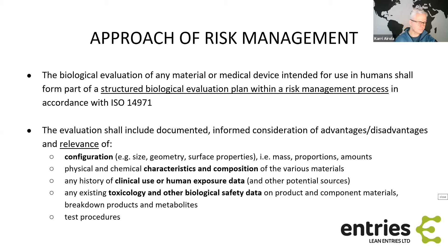So here again, it mentions leachable substances, which refers to parts 17 and 18, and degradation products you should be testing, and you should take into account the packaging materials you're using. Are they in direct or indirect contact with the medical device? Some of the packaging material you can neglect, but you need to present all the materials and all the components of your device in the biological evaluation. Those parts which are not in contact with the medical device could be left out of the evaluation and test plan, but you would need to justify that and show that this part can never contaminate the part which is going to be in contact with a patient.